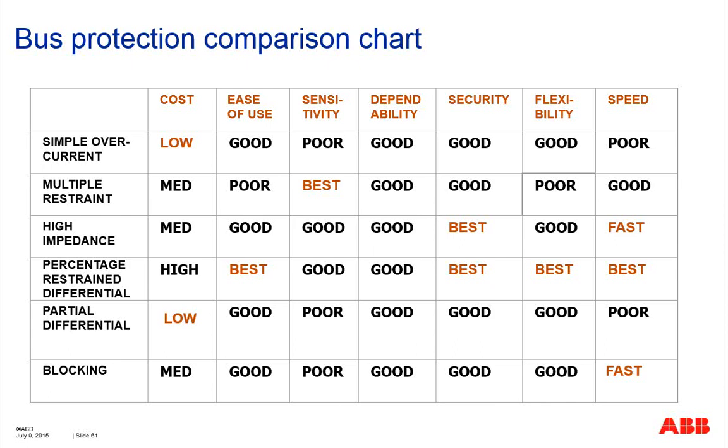The size is also slimmer. You don't need extra impedance, and you don't need to worry about the high voltage that can be induced during the fault, especially an external fault. So you don't need extra hardware or space for resistors and MOVs, for example.